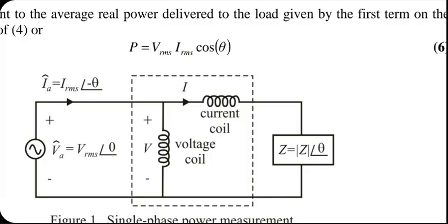But right now, in a power meter, you will not allow the deflection to go on for 360 degrees continuously. So you put a mechanical spring to counteract that torque, and the value is known to you. So it is possible to calibrate the deflection produced against the real power that the load is seeing. The same thing, by the way, here we are using the formula V RMS I RMS cos phi. It is all done in calibration in the instruments.